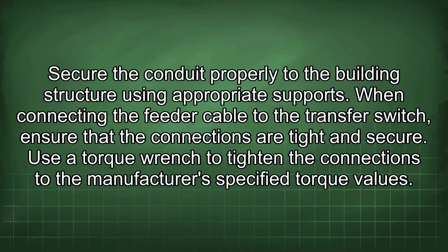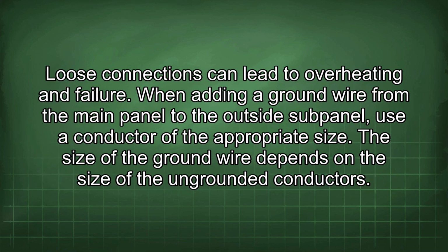When connecting the feeder cable to the transfer switch, ensure that the connections are tight and secure. Use a torque wrench to tighten the connections to the manufacturer's specified torque values. Loose connections can lead to overheating and failure.